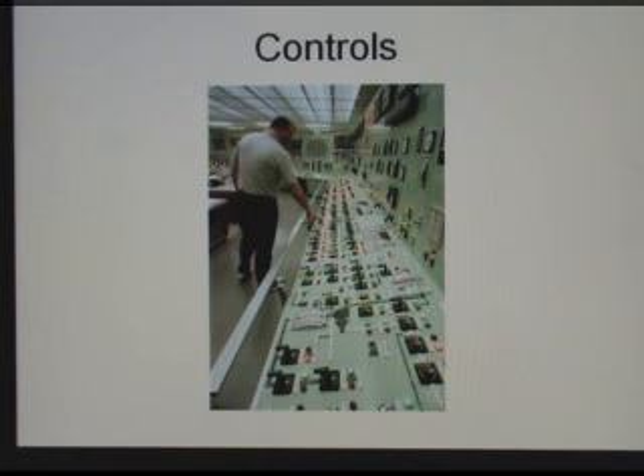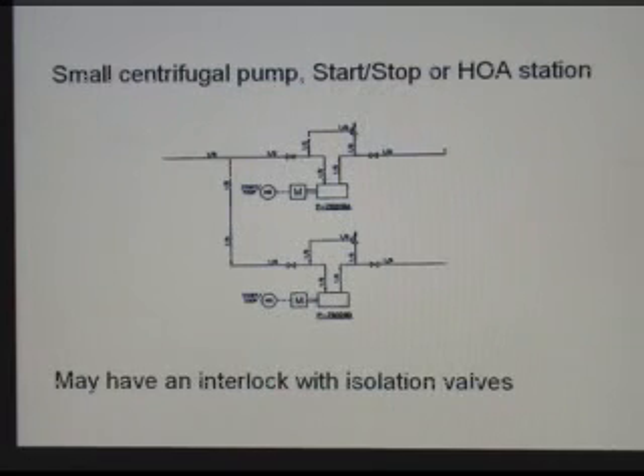Actually, this is a fairly typical control panel that you would see in a lot of the facilities that we've worked in. It's in the central control room. The controls that we deal with are on the machine. And so those could range in sophistication. For a small centrifugal pump, you may just have a start-stop button or a hand-off-auto station that's near the pump. And in some instances, you may actually have an interlock with an isolation valve so that you don't start the pump with a blocked discharge, just a simple way of protecting the pump from being damaged.